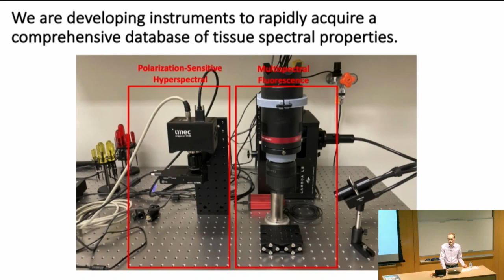This is in progress, so it's not quite complete, but the idea is that we have one section which will do multispectral fluorescence, and we'll have a series of filters that get rotated through. We have a xenon light source that comes in, and we can filter it for excitation. But then in series, we could collect some polarization-sensitive hyperspectral data. This is a hyperspectral camera with a rotatable polarizer in front of it, so we can probe different polarization states and get the whole hyperspectral cube. That really provides an ideal data set for generating these multispectral filter arrays for different diseases.